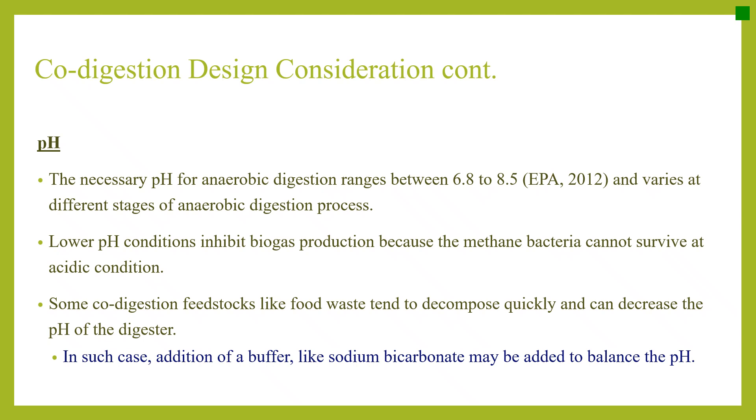The necessary pH for anaerobic digestion ranges between 6.8 to 8.5 and varies at different stages of the process. Lower pH conditions inhibit biogas production because methane bacteria cannot survive in acidic conditions. Some codigestion feedstocks like food waste tend to decompose quickly and can decrease the digester pH. In such cases, a buffer like sodium bicarbonate may be added to balance the pH.